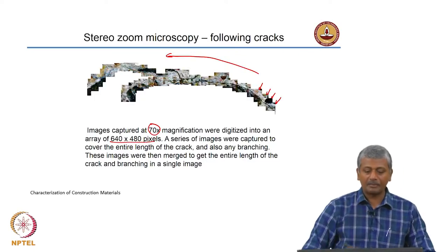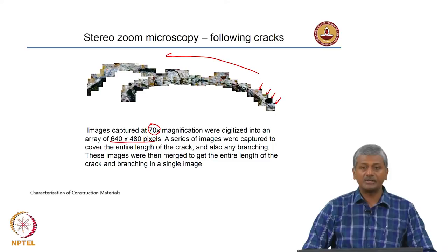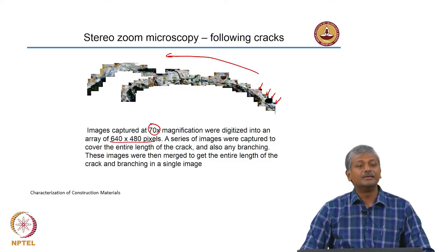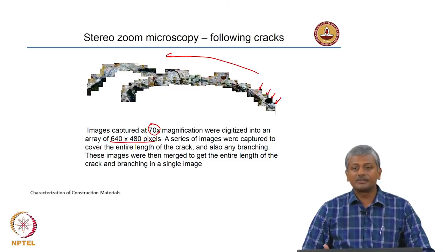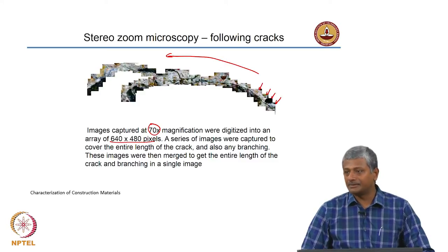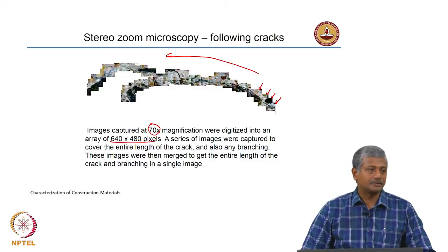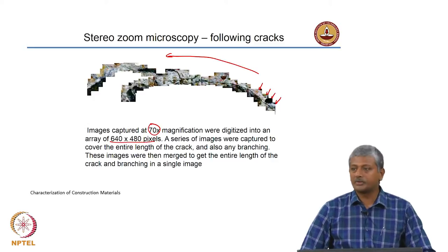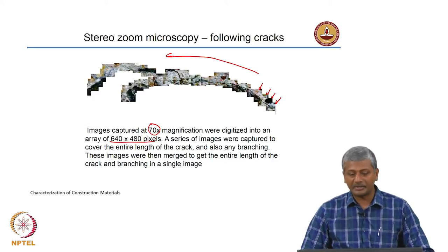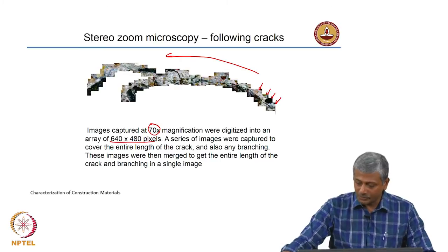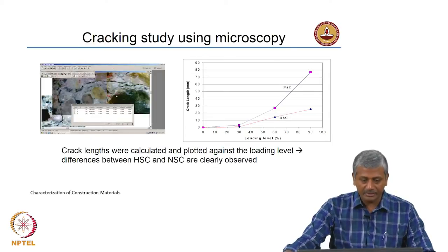Let us see what crack parameters were actually measured in this case. The most obvious measurement is the length of the crack. You can also measure approximate crack width at certain locations. That is what was actually done in this case.